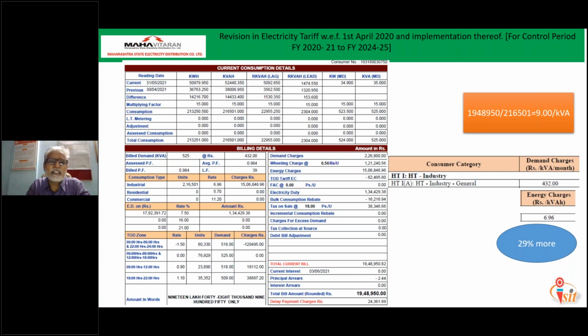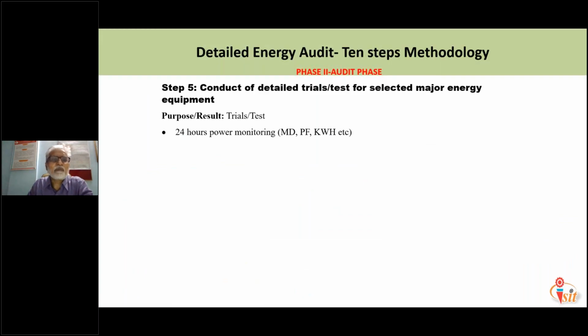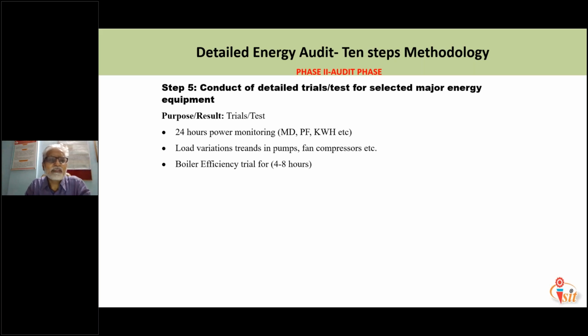We need to understand the art of reading electricity bills, and on the basis of the electricity bill we can also suggest some energy conservation patterns or steps for that particular company. Now next is step 5. Actually in industry we have to take some readings, so we need to decide whether to take readings for 1 hour, 2 hours, or 24 hours. Generally during audits we take 24-hour readings to monitor the maximum demand, power factor, as well as kWh. This is at the start of the supply, where the supply comes to that particular industry. There we put our power analyzer for 24 hours, and we monitor all these three, in addition to other parameters which we get from the power analyzer, continuously for 24 hours.